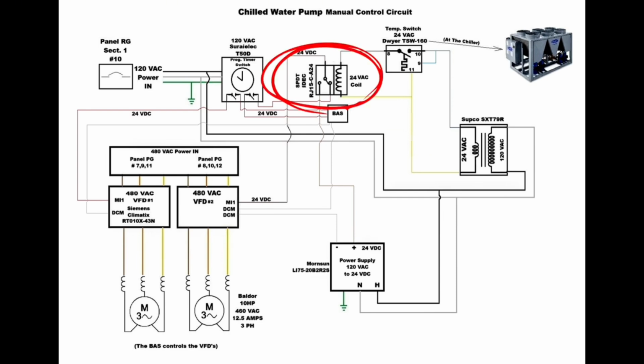This relay up here, if you notice, it's a single pole double throw. So in its normally closed position, the BAS will send its signal to the VFD. When that relay is energized by the safety switch up on the chiller, the switch will change positions and the normally open terminal will be closed. And that's where the 24 volts from our power supply will then go to the VFD to turn the VFD on. So that way we're never allowing the 24 volts from the BAS and the 24 volts from our power supply to be simultaneously trying to energize the VFD. So I hope that makes sense.